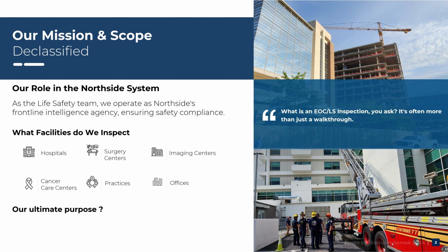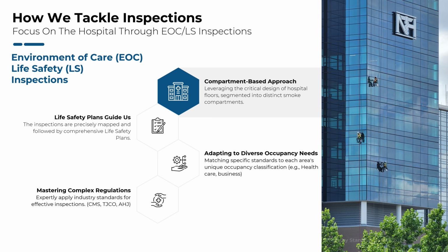Okay, so how do they manage this huge task across so many different places? How are these inspections structured? There must be a method. Oh, absolutely, it's very structured. These EOC and life safety inspections happen twice a year for every single facility, and the approach is based on a 4-point strategy. First, and this is key, they use a compartment-based approach. Compartments, like sections. Exactly, think of a hospital floor divided into distinct smoke compartments. These are areas separated by fire-rated walls and doors. The whole point is to limit smoke and fire spread in an emergency, creating safe zones.